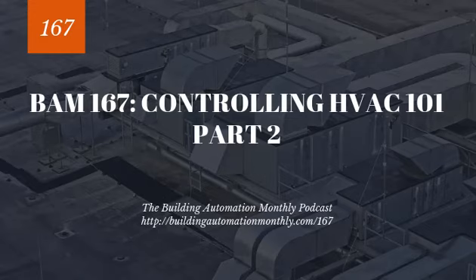So the primary thing you're going to be doing when you are working with a rooftop unit is you are typically going to be controlling to a zone or a set of zones. And typically you're not going to have variable flow. The main reason why you tend to not have variable flow is because these units are typically not serving boxes where it would make sense for you to have variable flow.